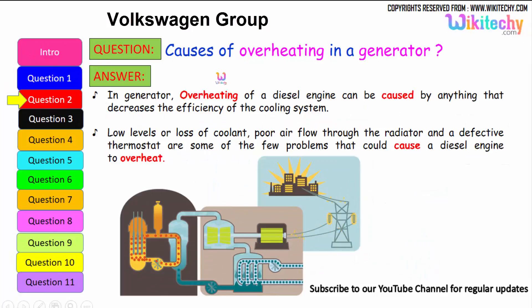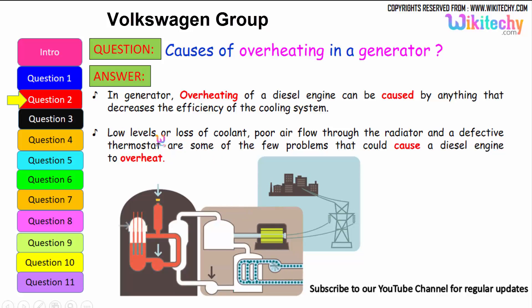Let us move on to the next question: causes of overheating in a generator. In a generator, overheating of a diesel engine can be caused by anything that decreases the efficiency of the cooling system. It can be due to the loss of coolant or low levels of the coolant, poor air flow through the radiators, and a defective thermostat, which are some of the few problems that could cause a diesel engine or a generator to overheat.